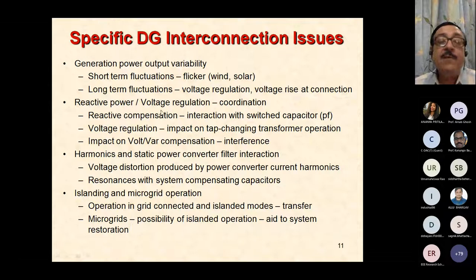You can have reactive power and voltage regulation coordination at the point using the same converters. You can have reactive compensation also along with interaction with switched capacitors. I will discuss this later, interaction with switched capacitor networks. You have voltage regulation problems, impact on tap changing transformer operation and on volts and VAR compensation. So there will be interferences. We'll see these problems. The moment we have the distributed generation converters connected to the line, these types of problems come up. Along with that, we have the problem of harmonics and static power converter filter interaction. These converters inject a lot of harmonics into the supply lines and they in turn distort the supply voltage to the consumers. We will take a look at it later on.